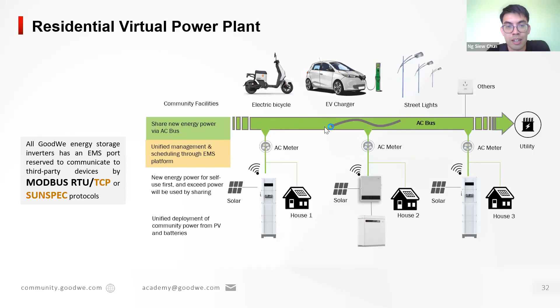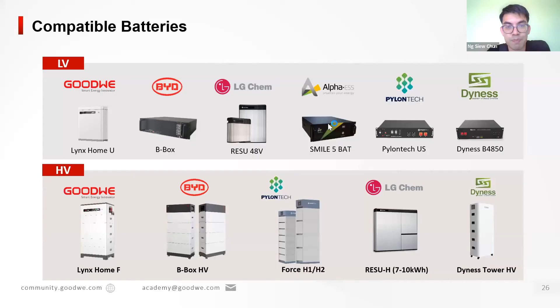How does the hybrid on-grid inverter work during a grid outage? Does it need an ATS? Like I mentioned earlier, our switchover is integrated into the hybrid inverter, so you would not need an additional ATS installed externally. Let me go back to the slide that shows the UPS level. This topology is integrated in our inverter. You can see that we have two outputs, on-grid output and backup output. When the grid is available, this relay is closed and this relay is closed. So the inverter power output will be supplied to the on-grid output as well as to the critical loads. The critical loads and the grid-connected loads are at the same connection point.